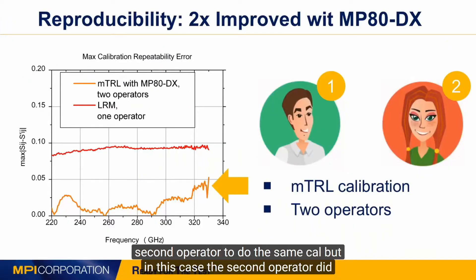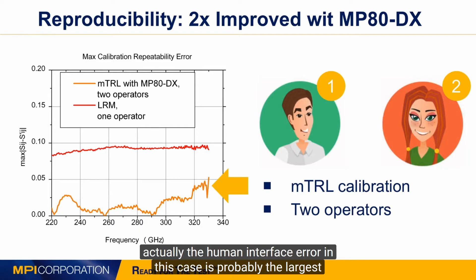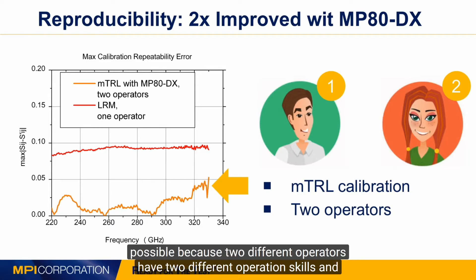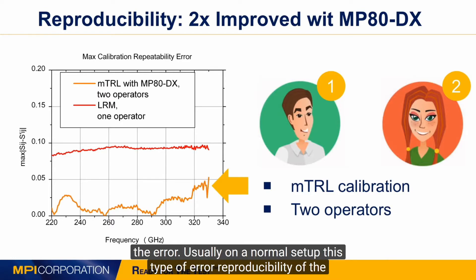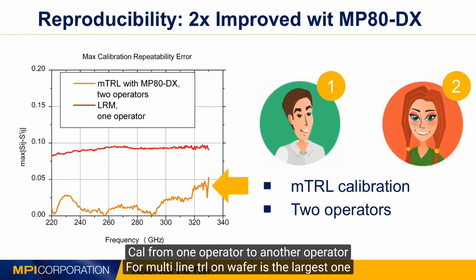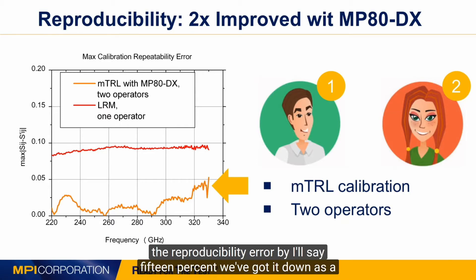We then did another experiment: we asked a second operator to perform the same calibration. Both operators independently performed multi-line TRL calibration, each moving the probes from each other. The human interface error in this case is probably the largest possible, since two different operators have different skill levels and each repositioning can introduce different types of error. On a normal setup, this operator-to-operator reproducibility error for multi-line TRL is the largest source. In our case, with the Digital X feature, we reduced the reproducibility error by about 50% — down to a maximum of 5% between two operators — significantly increasing measurement reproducibility.